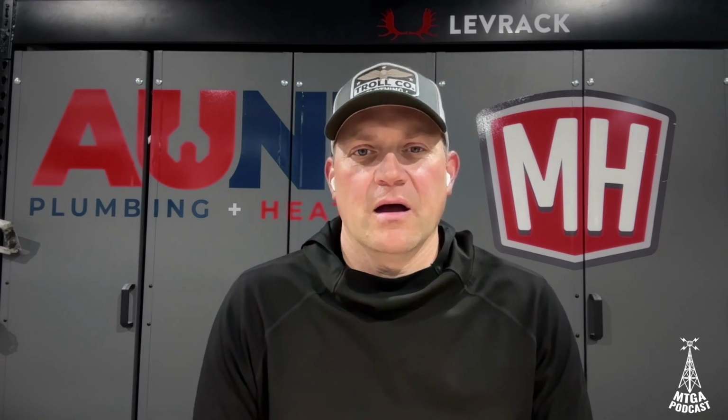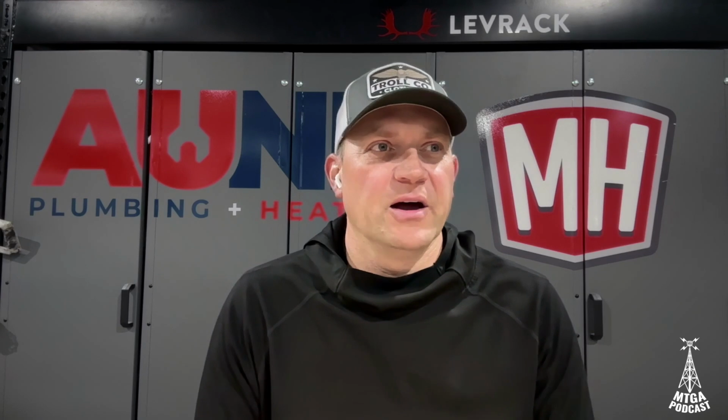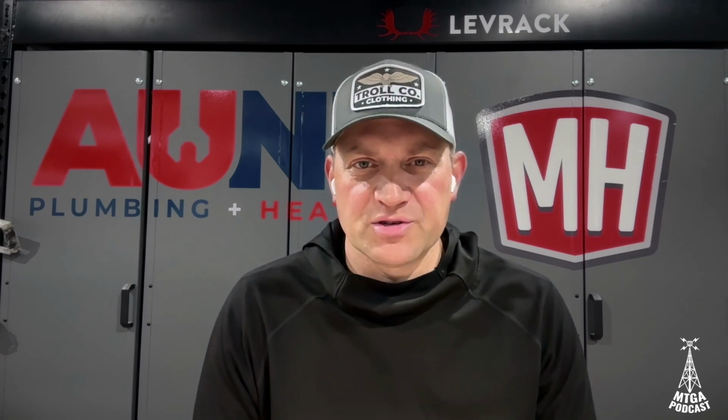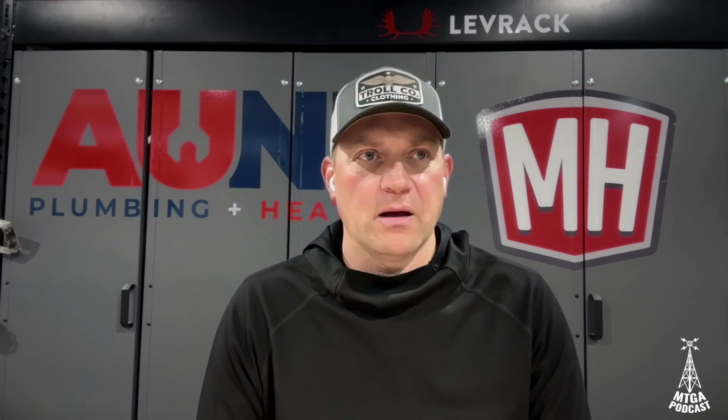The only other thing I think, unless I just missed you covering it, was the indoor to outdoor unit wire. Oh, there's a communication cable. Yep, I missed it completely. There's a shielded, 22 gauge, stranded shielded twisted pair wire that they want. It's field supplied. Yep.